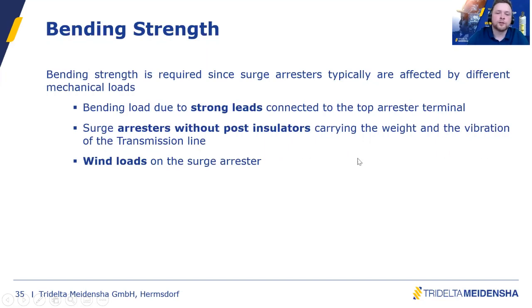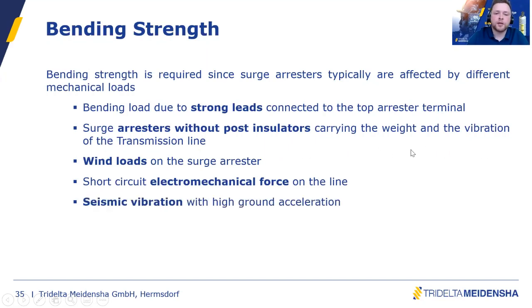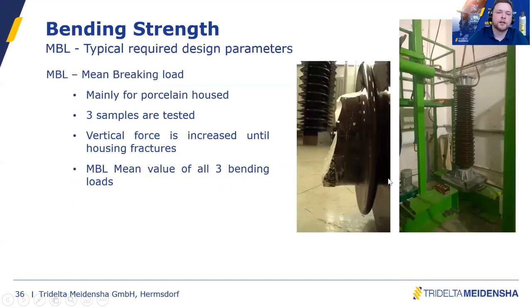We have wind loads on the surge arrestor itself. We have electromechanical force on the line. And we also have seismic vibration on the ground terminal of the surge arrestor. So those things have to be considered when you design a surge arrestor. And of course, there are standardized values we have to fulfill to classify our surge arrestor for certain applications.